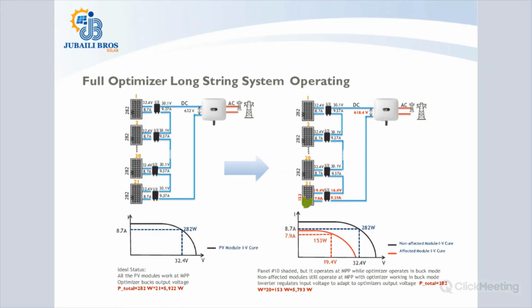Sorry about that. So we could see from what is happening here that you can see clearly that the output of the PV optimizers has bucked the system. So the current has increased, the voltage has decreased. So as the current increases, the voltage decreases, and you can see in this instance that the current is still 9.37 amps, which is still lower than the 30 amps that we said. So it has bucked this system, but the current is still in a safe state, and it has enabled us to increase the number of PV modules in this string and make it longer than the traditional case.